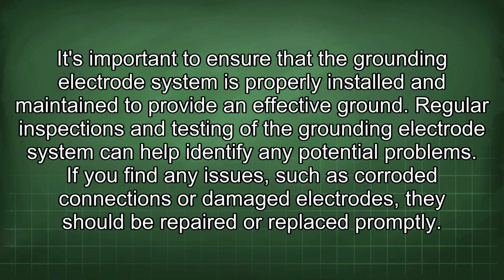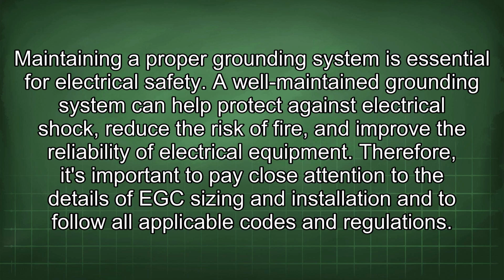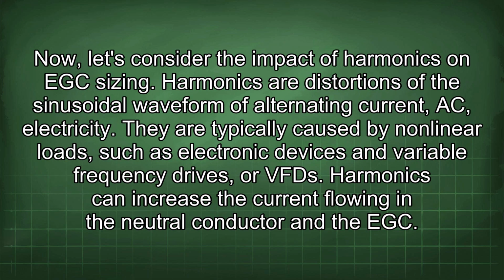Regular inspections and testing of the grounding electrode system can help identify any potential problems. If you find any issues, such as corroded connections or damaged electrodes, they should be repaired or replaced promptly. Maintaining a proper grounding system is essential for electrical safety. A well-maintained grounding system can help protect against electrical shock, reduce the risk of fire, and improve the reliability of electrical equipment. Therefore, it's important to pay close attention to the details of EGC sizing and installation and to follow all applicable codes and regulations. Now let's consider the impact of harmonics on EGC sizing.